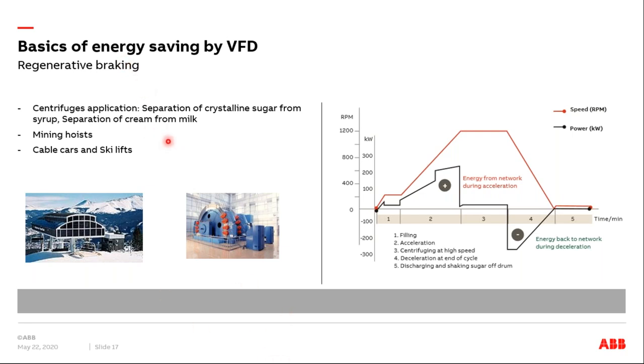The idea of using regenerative braking in all these applications is to get the energy back during the deceleration period of these applications. Of course there is energy saving because you are getting the energy back to the grid. But the more important advantage is that if you use VFDs to do this regenerative braking, you are increasing the productivity of the system and also reducing the maintenance needs of the system. I'll talk a little bit about this in later slides.